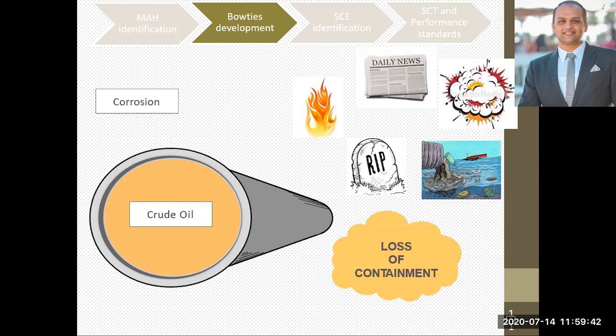Okay, so the last question for today's session, someone is asking how to ensure that the sensors and barriers are working properly at any time. We will go back to the performance standard. By developing the performance standard, we put for the safety instrumented systems and basic process control systems, in the functionality, that we have to test the sensor in a periodic manner and make sure that the levels are correct and the tuning is correct as well. And if this is okay, you can name it as adequate for its purpose.